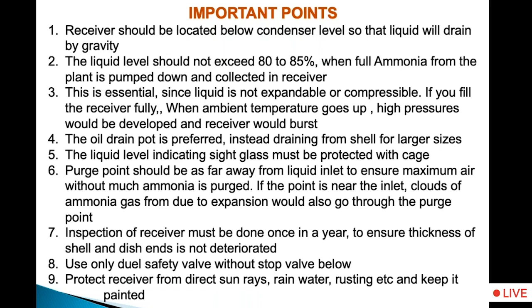Use only a dual safety valve without a stop valve below. Most people use a stop valve because the dual safety valve is not of good quality, and when I ask them why they are using this valve, they say, oh, the safety valve leaks. And therefore, to prevent that... now there is no point in having a safety valve when you have a stop valve below. In 90% of plants, if you see, they still use a stop valve below the safety valve, which is a wrong practice, not recommended by the standards.